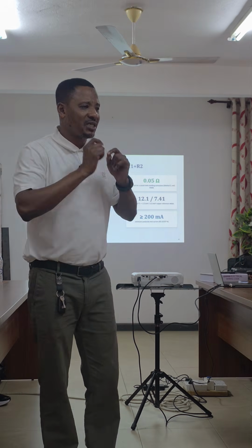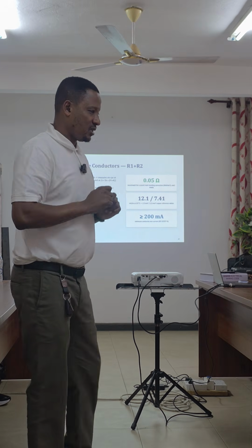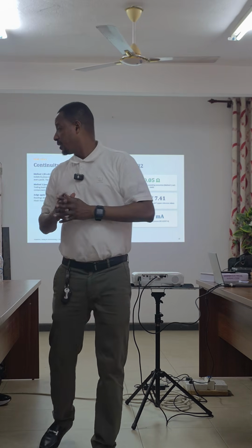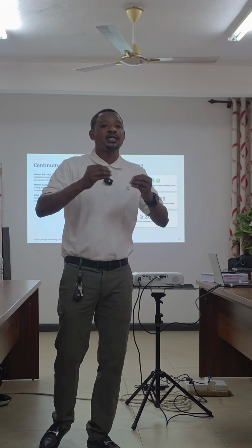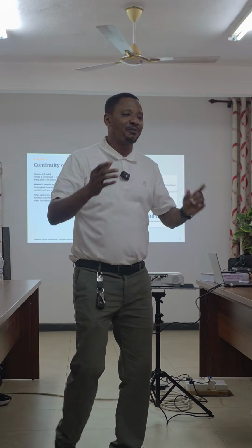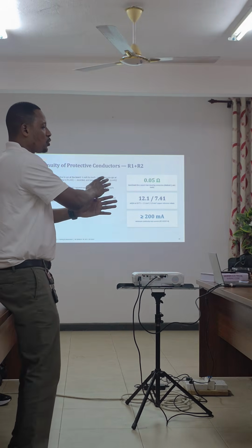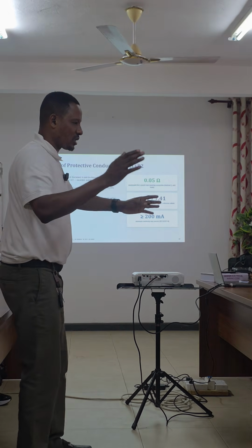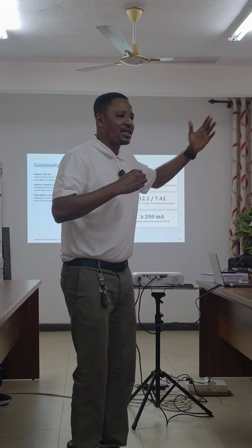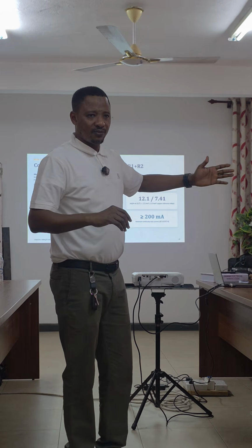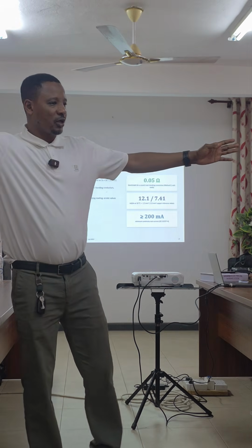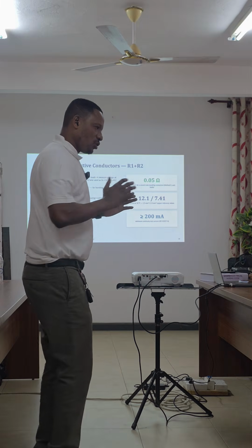And mostly the emphasis is always on what? The CPC. Who knows what the full meaning of CPC is? Yes, so it's circuit protective conductor. That is what the CPC is. That is the emphasis. But now you are being required to test continuity of CPC, live, neutral, and earth, all of them. So when you establish continuity, it means that you are sure that circuit has nothing wrong. When you turn on the supply, current will flow all the way to what? The utilization point. You are good.